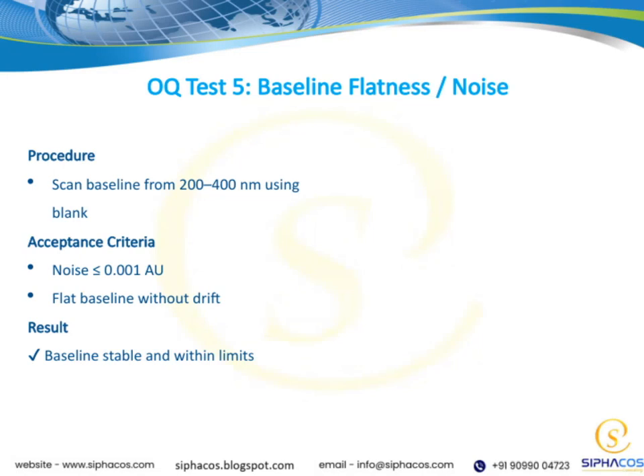Now, let's take a look at OQ Test 5, which focuses on baseline flatness and noise. The procedure involves scanning the baseline from 200 to 400 nanometers using a blank sample. This range is chosen to ensure we accurately capture any irregularities or fluctuations in the baseline signal. The main goal here is to check for stability and consistency in the baseline readings. When it comes to acceptance criteria, we want to see that the noise level is less than or equal to 0.001 absorbance units. That's a very tight limit, but it's important because it indicates a clean and stable system.